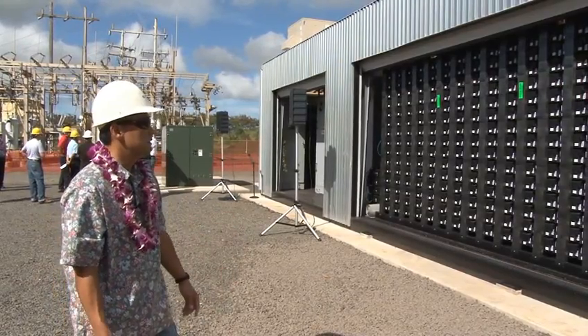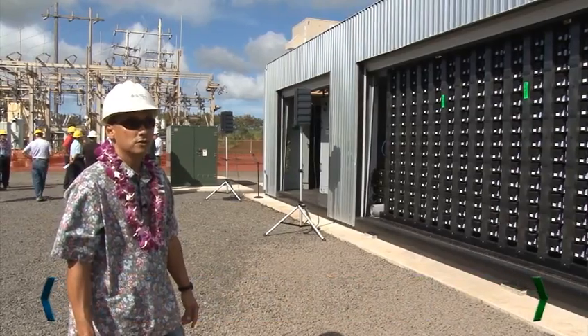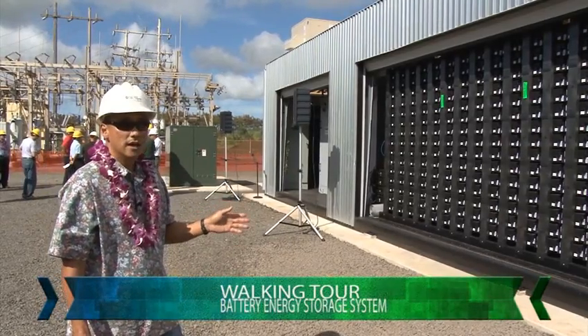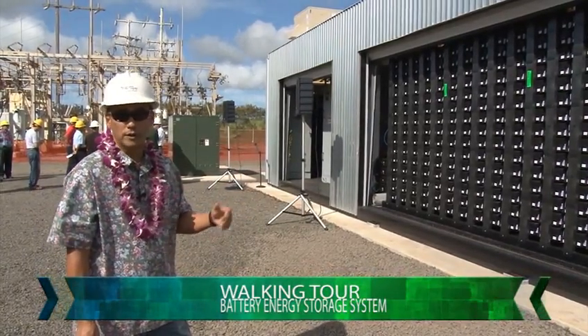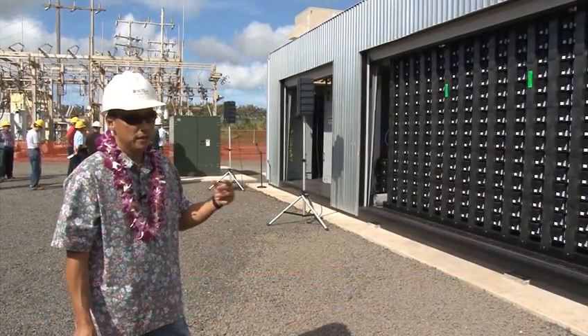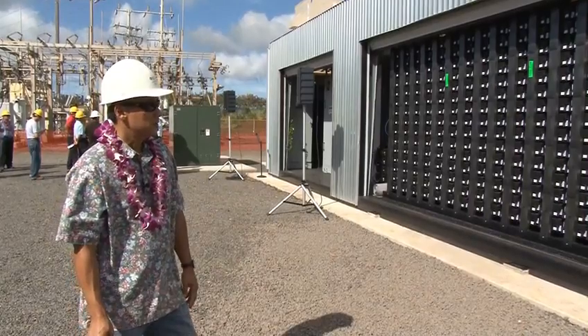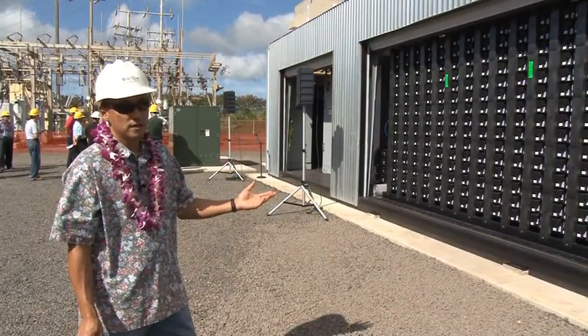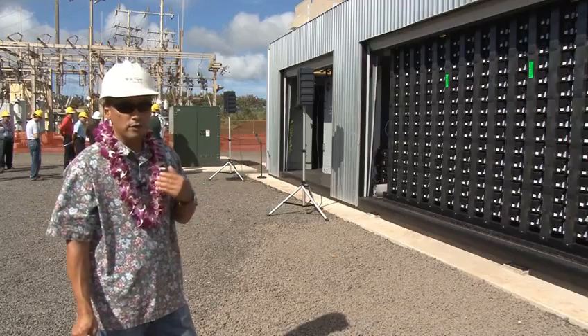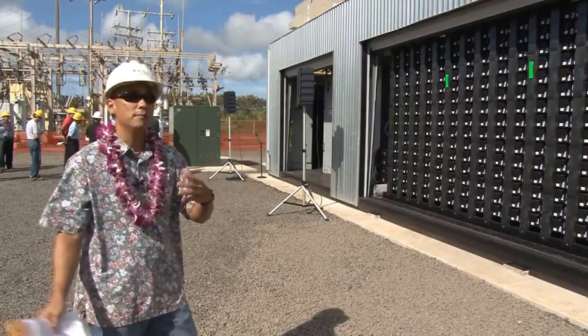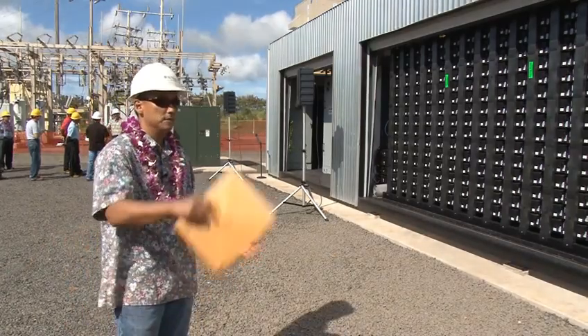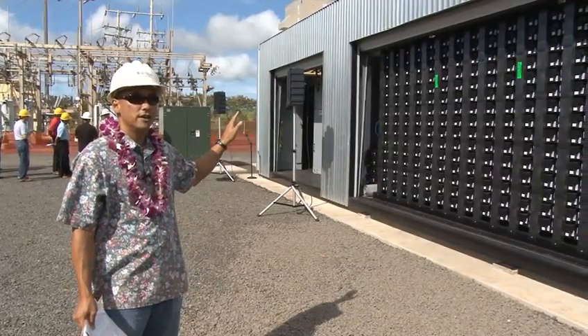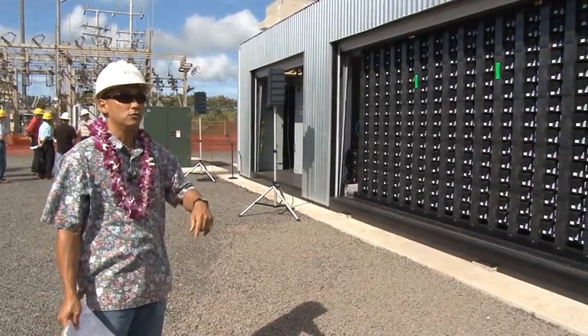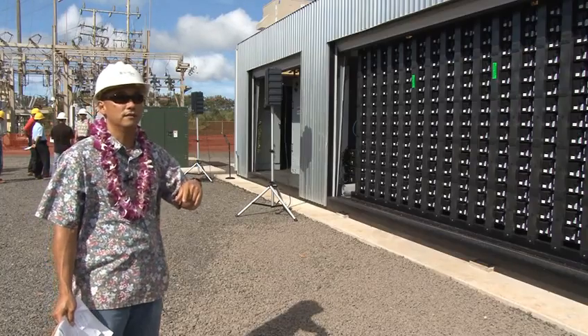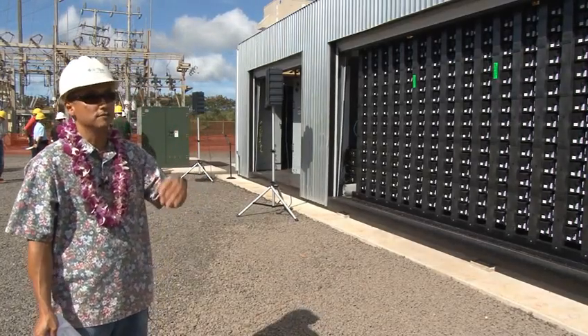I did forget to mention, this is the state's only utility-owned battery storage. They have similar systems like this on Lanai and Maui and Oahu and the wind farm, but those are developer-owned. So the utility cannot use it for grid support, which is a key part for us. It's not just mitigating the renewables and increasing penetration, but being able to support our grid. So we have full control over this. In fact, our grid response overrides the PV mitigation. So when the PV comes online, and let's say the PV drops and it smooths it out, if we have an event like a lost generation right during that time, it'll kick in to support the grid event and not the PV event, because that's a bigger event for us than just the variations of the PV.